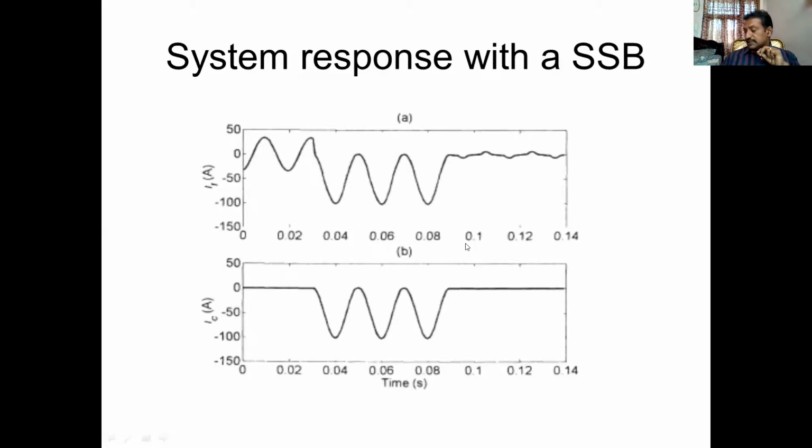Also note that after the thyristor switch is blocked, the current does not become equal to 0. Why does this happen? Because a small amount of feeder current still flows through the zinc oxide arrestor and the snubber circuit. This current can be interrupted by opening a conventional switch.